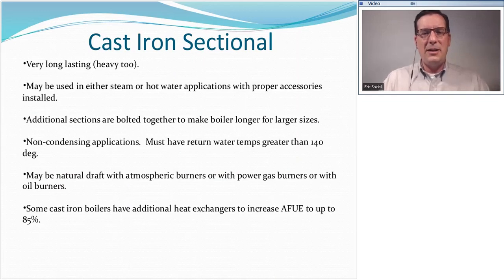Additional sections are bolted together to make the boiler simply longer or wider, depending on your perspective, for larger sizes. All cast iron boilers, with one notable exception, are what we call non-condensing applications. This means they need to have return water temperatures higher than 140 degrees Fahrenheit. Regardless of what fuel we're dealing with, 130 degrees is approximately the condensing point of the water vapor component of products of combustion. And we do not want to have the surfaces of our cast iron boiler accumulating water vapor on them. And that will happen if we're constantly flowing cold water into the boiler. So cast iron boilers need to be designed so that the water coming back from the system is greater than 140 degrees. And if it's not going to be greater than 140 degrees, special considerations need to be taken.